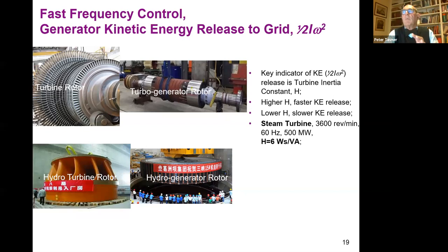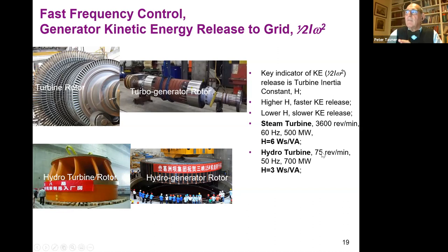A steam turbine, like the one at the top, has an H of 6, which is very good, that's high. The hydro turbine at the bottom has a lower H, about 3. It's still not bad. You may wonder why it's so large yet H is smaller. Well, looking at the formula, it's a half I omega squared. This rotor has an enormous inertia, but its speed is quite slow, 75 revs per minute, so the omega squared is quite small.